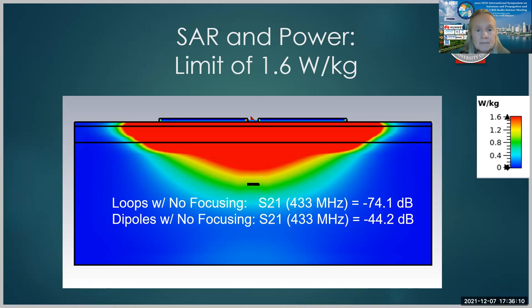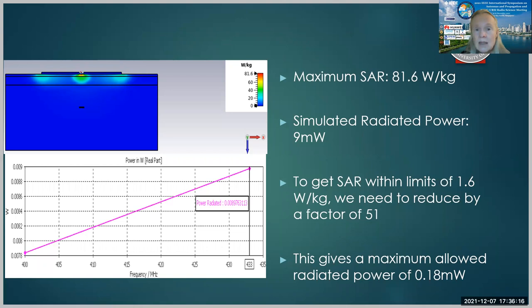Now, if we need to limit the SAR to 1.6 watts per kilogram, which we do, the maximum SAR shown in the previous picture was 81.6 watts. And that's simulated with nine milliwatts of power. So to get the SAR down to within limits of 1.6, we'd need to decrease this by a factor of 51, which would give a maximum allowed radiated power of 0.18 milliwatts.